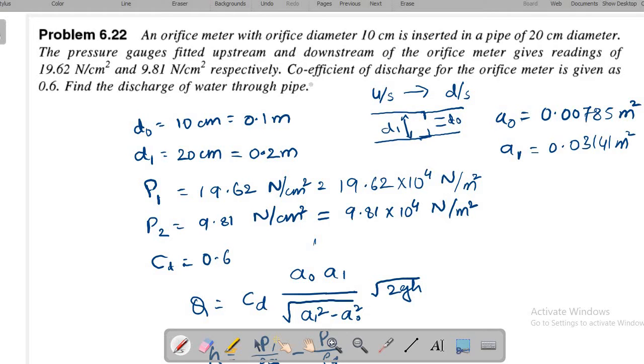Problem 1: An orifice meter with orifice diameter 10 cm is inserted in a pipe of 20 cm diameter. Pressure gauges fitted upstream and downstream give readings of 19.62 N/cm² and 9.81 N/cm² respectively. The coefficient of discharge is 0.6. Find the discharge of water.